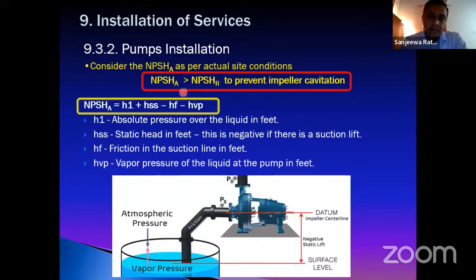But NPSHA is net positive suction head available. This availability depends on the site situation, the site condition. So this NPSHA value must be higher than the NPSHR. NPSHA can be calculated with a simple formula, but it has to be calculated at site as per the site requirement. Otherwise, sometimes there may be problems after installation, and at that time nothing can be done. So the contractor must be vigilant in selecting the pumps.